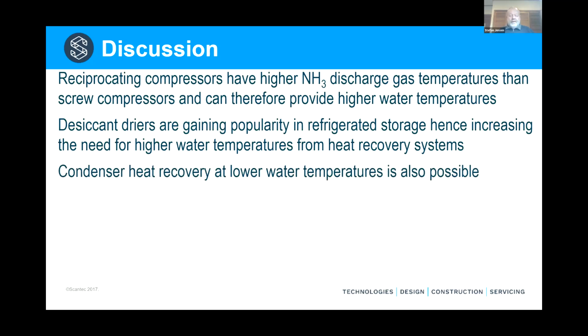We can also recover all the 88% condenser heat, of course, but that is at a much lower temperature, and it may be a problem finding a use for those lower temperatures unless another high temperature heat pump is added to the system, like Jared was alluding to before.